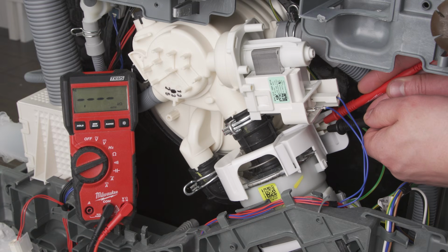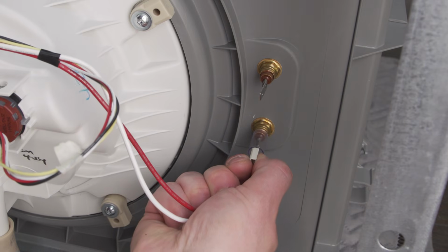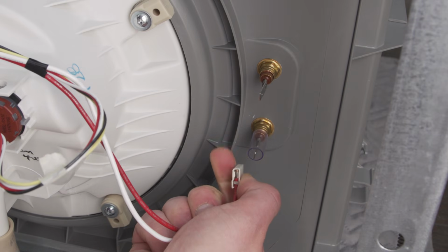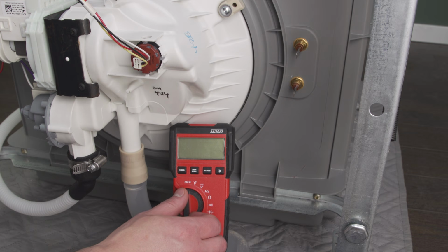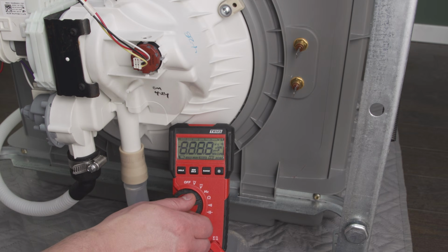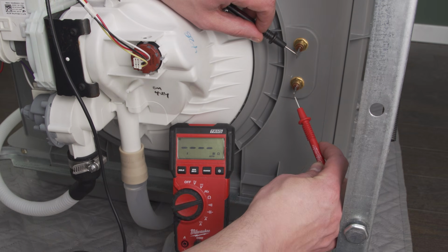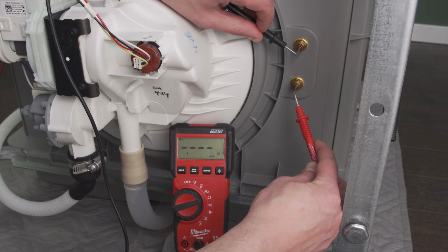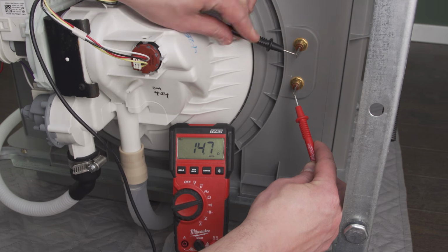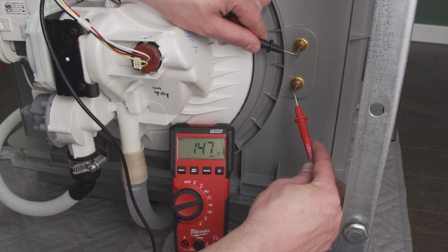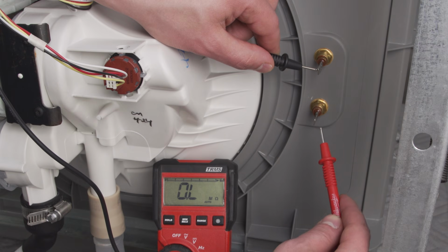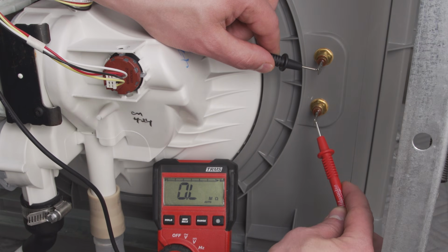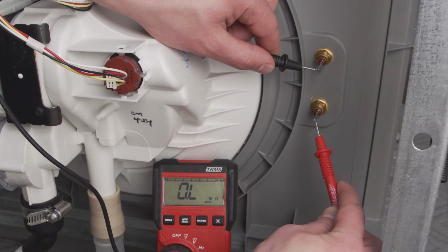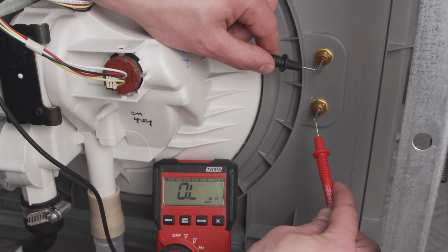In all models, you can test the element from the bottom. First, disconnect the wires. Set your multimeter to the resistance setting. Touch each probe to each terminal. There should be a resistance reading of 10 to 30 ohms. If there is no continuity, an infinite reading, or a resistance in the millions of ohms, then the element has failed and should be replaced.